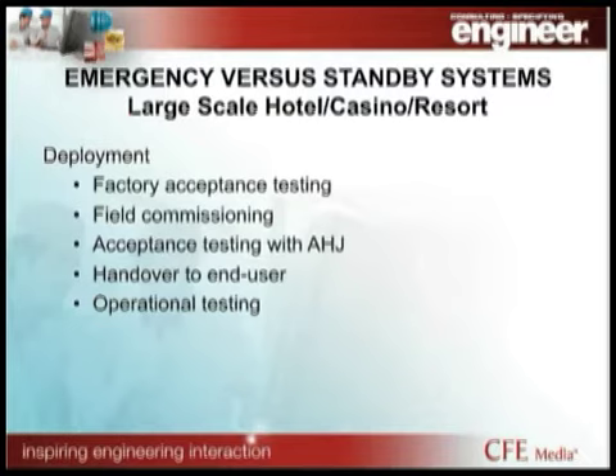And the nice thing about doing that in the factory is you don't have building load connected, you don't have all the chaos that's going on towards the end of the job, and it's in a controlled environment where they can make changes. The goal is that you really kick the tires hard on that equipment before it shows up on site for field commissioning. And ideally for field commissioning, what you should be worried about is connecting the equipment all together and then running it as one global system.